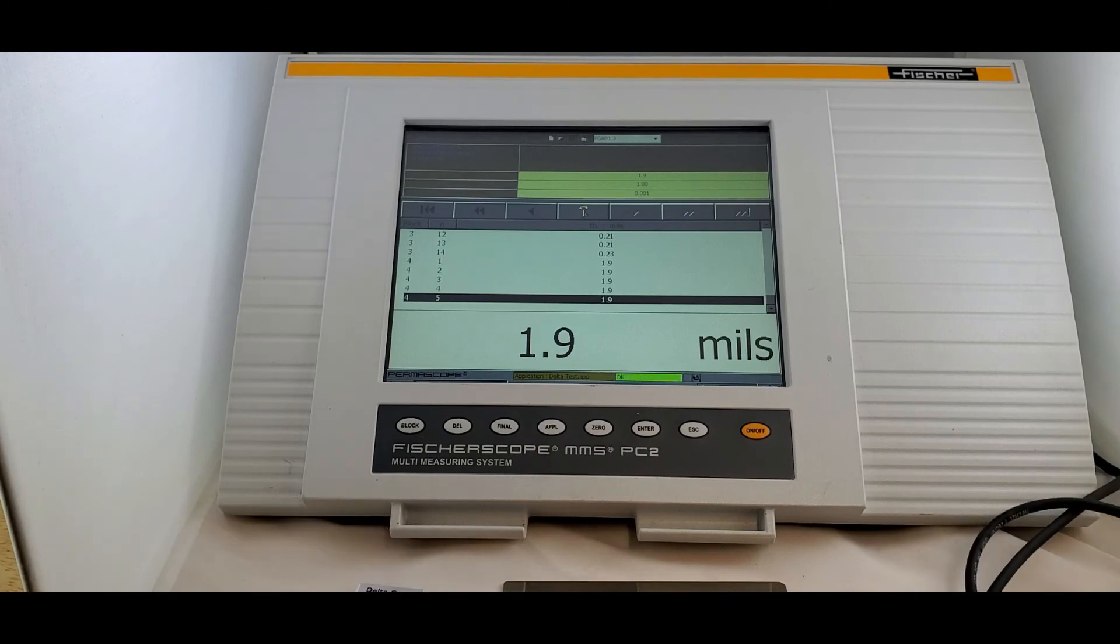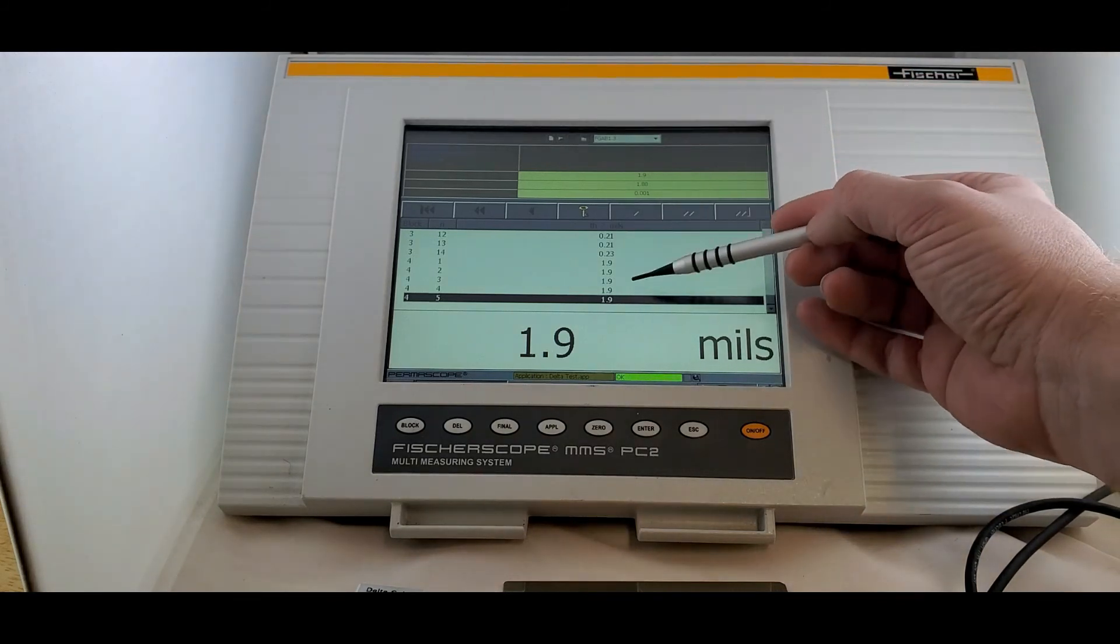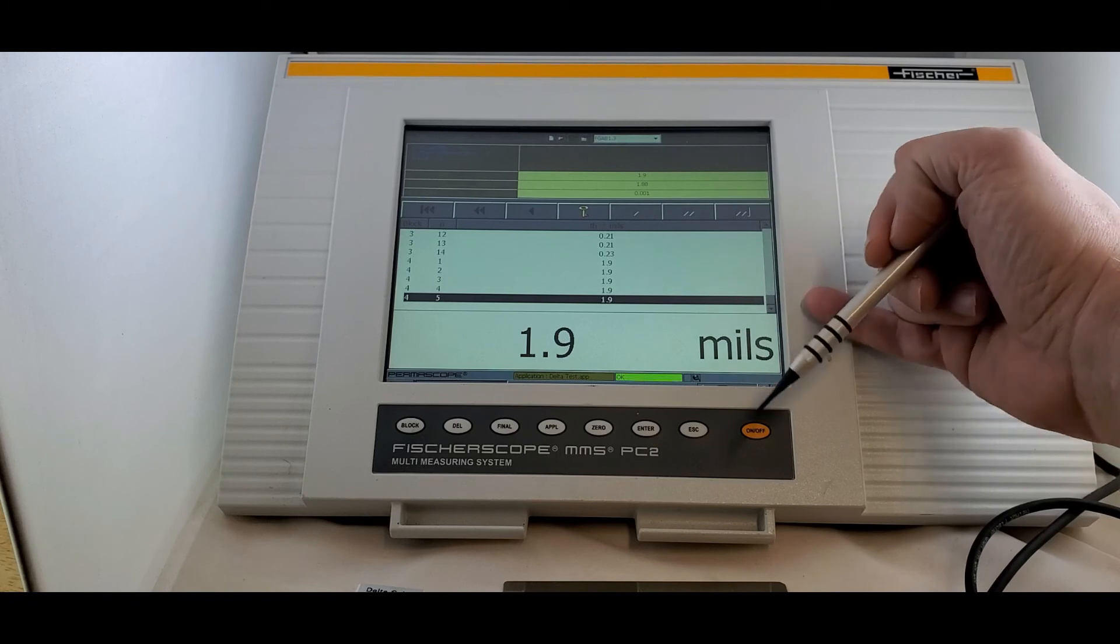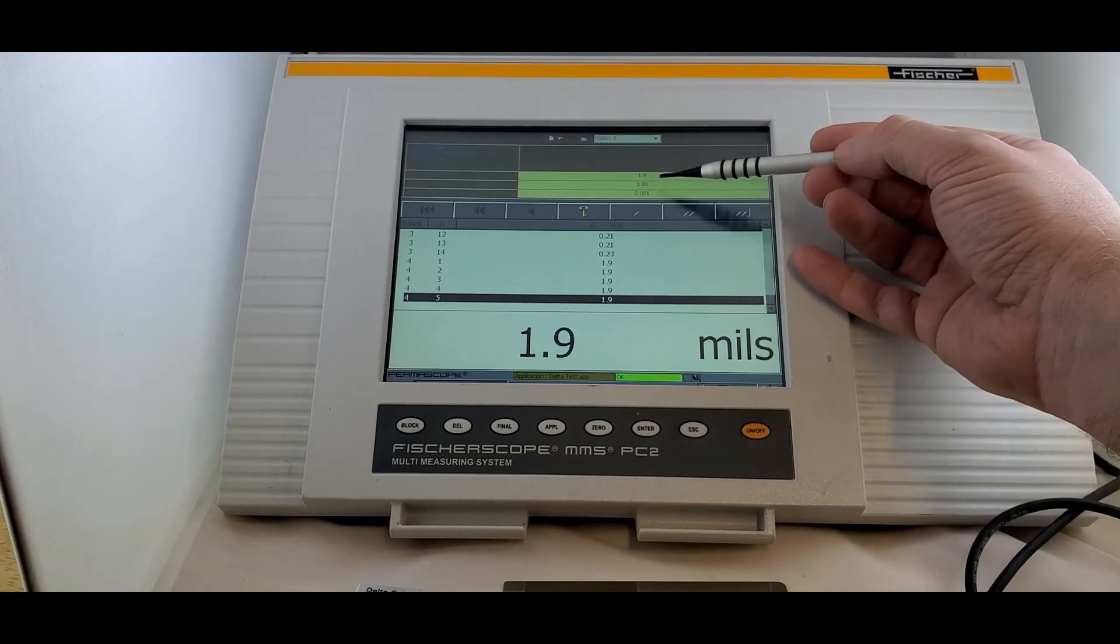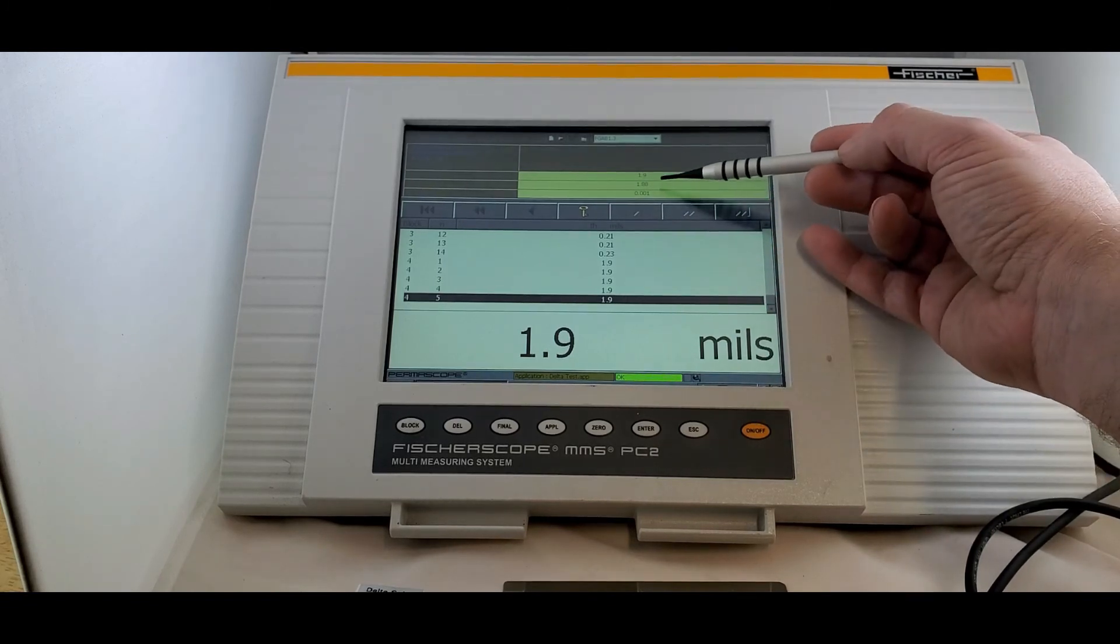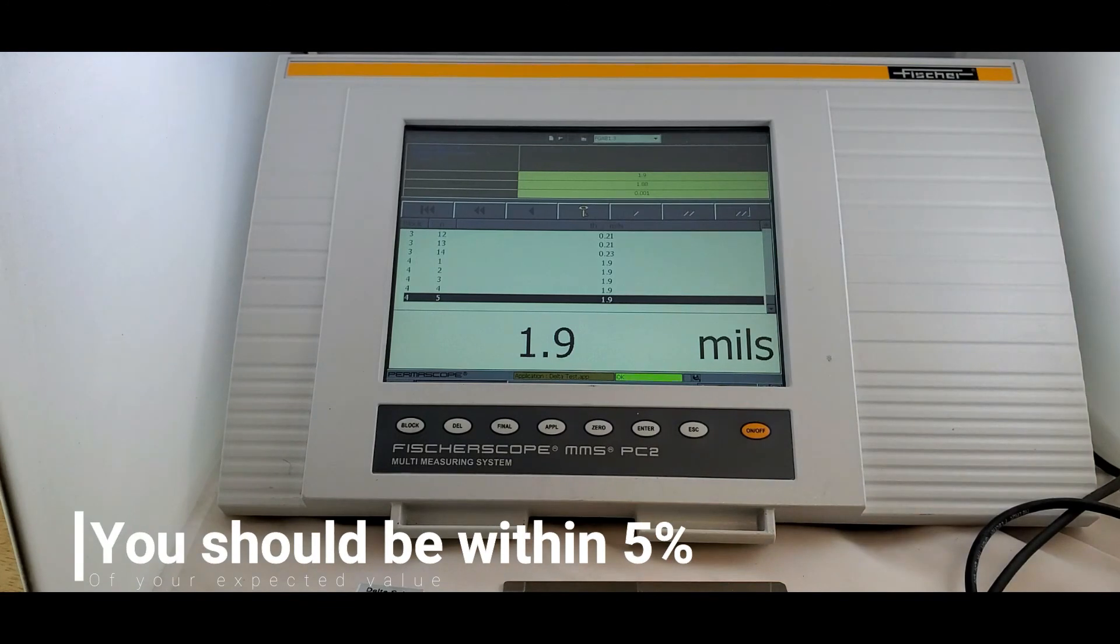Again, just doing five measurements just for the sake of getting a fairly decent sized batch of numbers. And you can see each reading was about 1.9, which is really good. The mean value of those five measurements that I took was 1.88. We're in calibration.